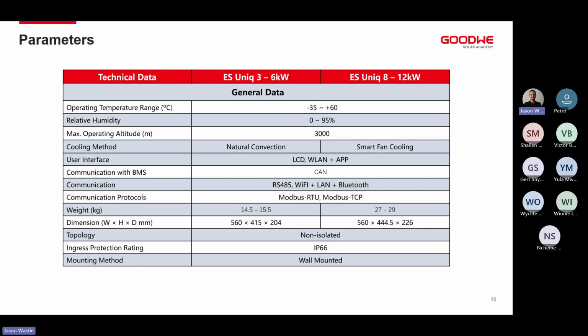We use that in our smaller residential spaces where we don't have the physical space or capacity to install these inverters outdoors, even though they are IP66 rated and can be installed outdoors. Not every application requires that. We can install these inverters indoors. They're relatively close to silent and they don't require any additional cooling. They have natural convection cooling, meaning it cools from bottom to top. It just ventilates heat through the inverter itself and doesn't use any forced air cooling on the units.